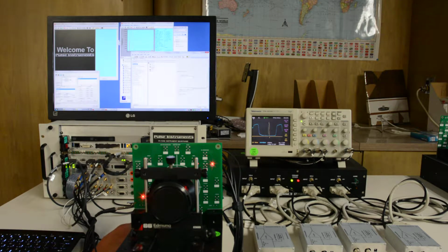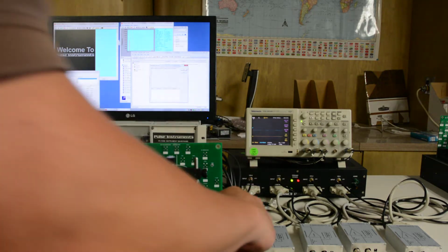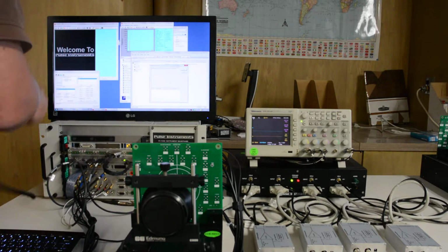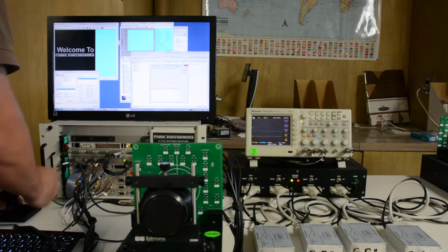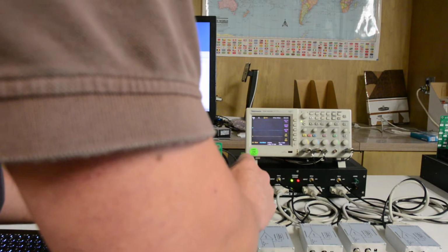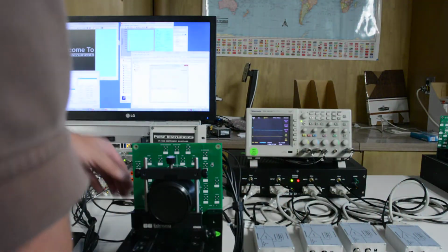First I'm going to choose the disconnect test plan, and when I run this, it will shut off all the clocks and biases, making it safe to connect or disconnect the focal plane. I'm going to apply my wrist strap, remove this test adapter, and install the device under test. We're now ready to begin testing.